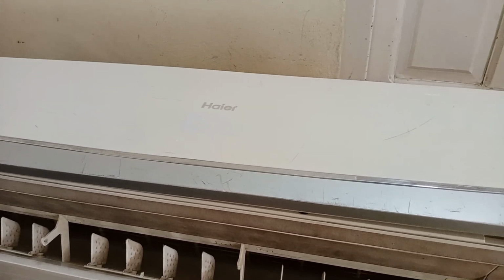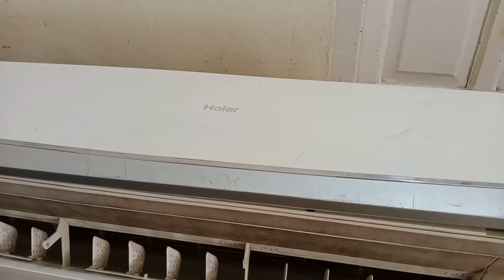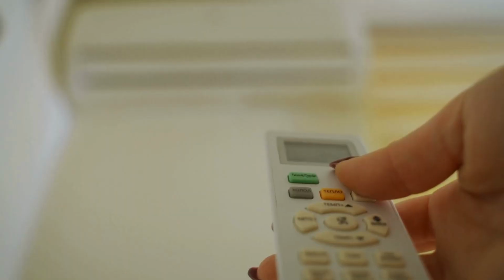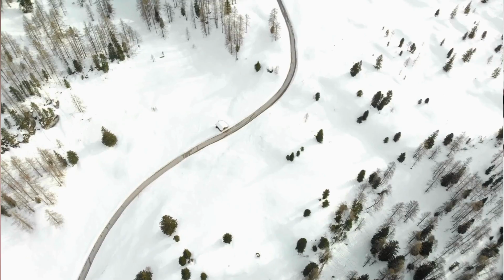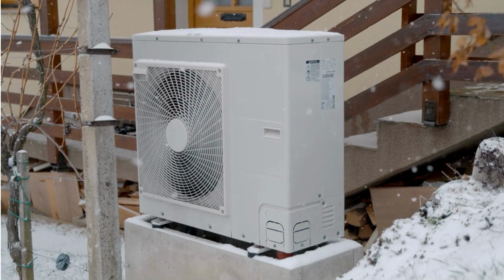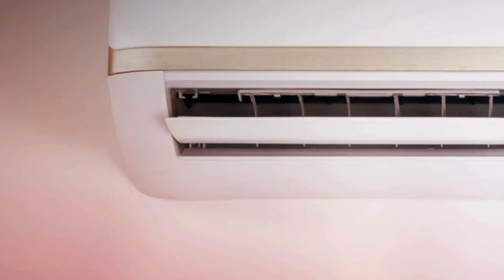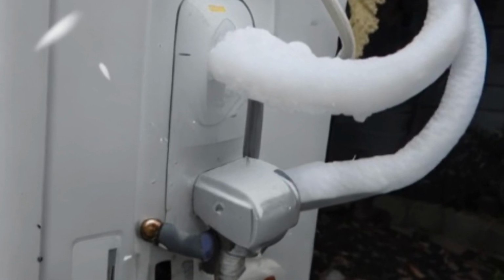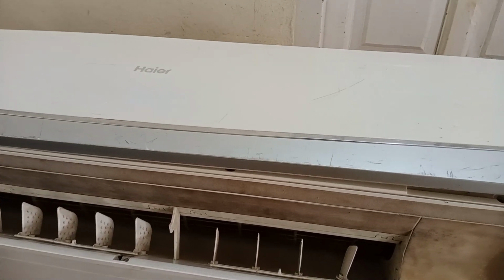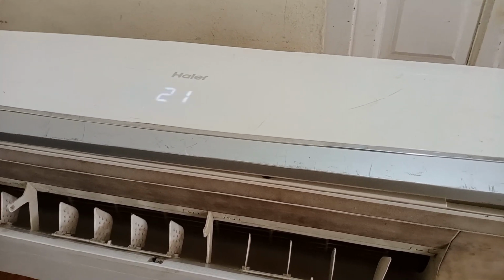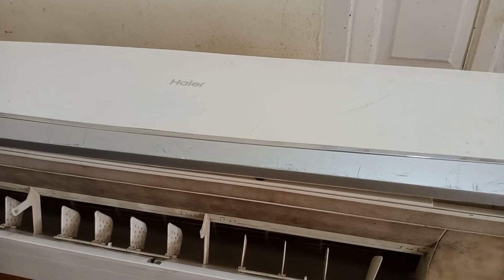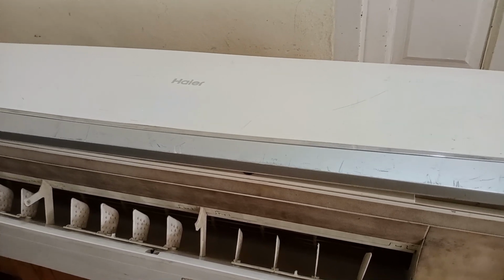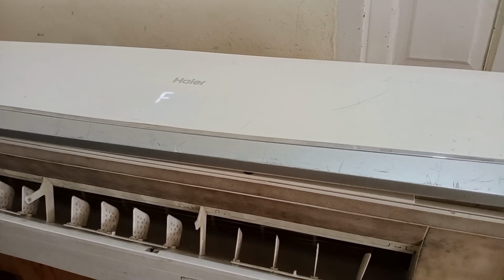Now, let's discuss the connection between the frost-removing function and the outdoor unit. When you run your unit in heating mode during the winter, the outdoor unit gets cold while the indoor unit provides heat. To address the buildup of excessive frost in the system, Haier has designed this function. The thermistor is responsible for monitoring and controlling the frost buildup. However, when this thermistor becomes short-circuited or faulty, it results in the F-21 error.